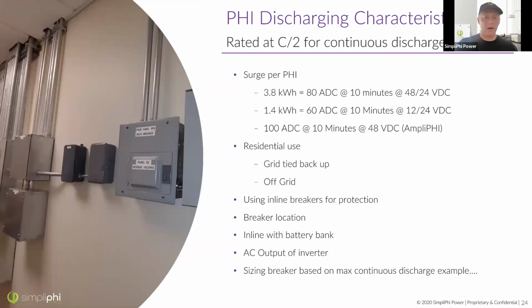Now, a lot of our customers have a large inverter that they barely use any of the power of. So let's say they've got a 6 kilowatt inverter and they only really use a 2 kilowatt load. So they're saying, well, SimpliPhi is going to require me to install 4 batteries on this 6 kilowatt inverter, but I really only think I need 2 batteries. So what they'll try to do is limit the discharge using a breaker for overcurrent protection. We're going to talk about this. I'm not saying that it's never possible, but I don't think it is a good idea.